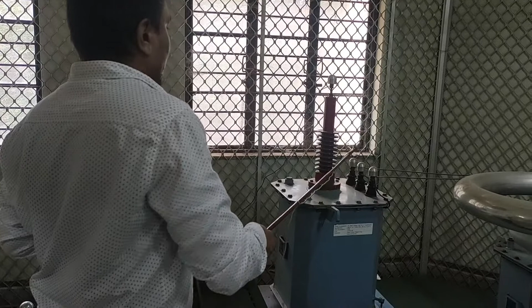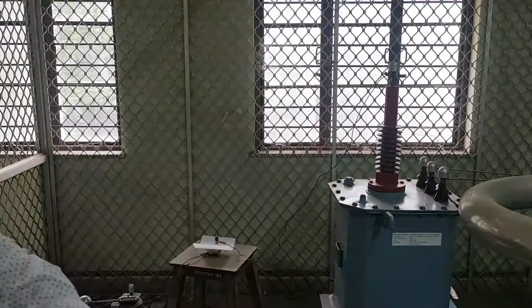Now the supply is off. The supply is off, but we are still discharging this test setup. Now we can discharge the electrode. So now we are safe. We can touch that instrument or HT instrument, and now here I am collecting the sample.